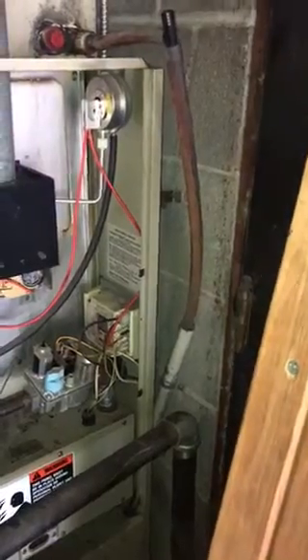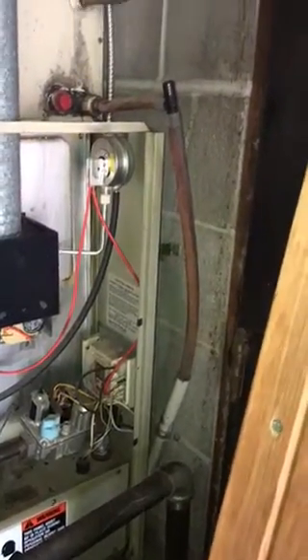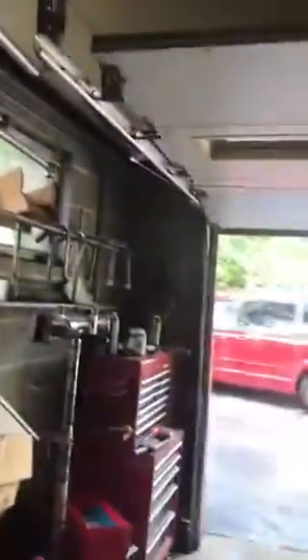The condensate drain just goes out onto the yard, so I'm just going to stick with that because there's really no other place to go. The Freon lines run here up across, so we're going to have to actually move a lot of this. And then they come down here and they do go out — here they are right here, and then they go out to the yard back here.